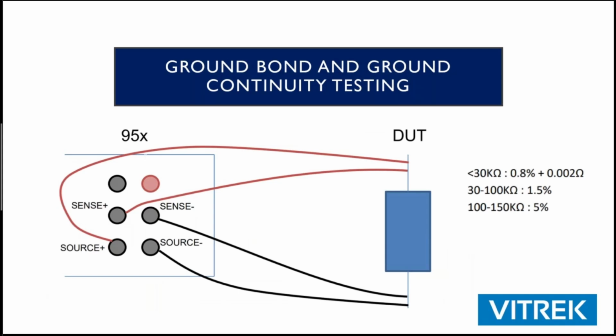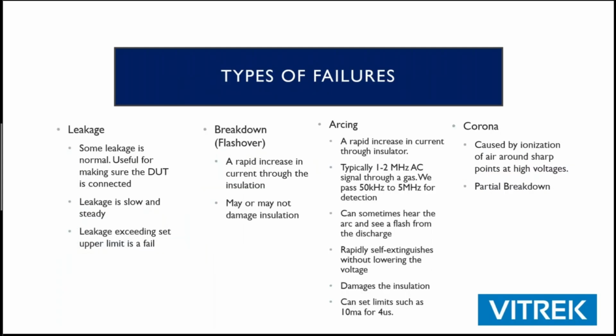Here's an image on how ground bond is going to work on your DUT. Once again, everything's going to be a little bit different. But the thing to remember here is that we're supplying a current, and we're measuring the voltage drop across your DUT. And with the tester, you're going to be setting up parameters, and your product must fall into that window to pass. All right, so there's at least 4 ways you can fail. If you've set a leakage current limit, you could simply exceed that limit. That limit could be 5 milliamps and your product could be 6 milliamps. If that's the case, it's not necessarily the end of the world. You might have to look at why. It could just be a capacitive or resistive issue, which might be acceptable.